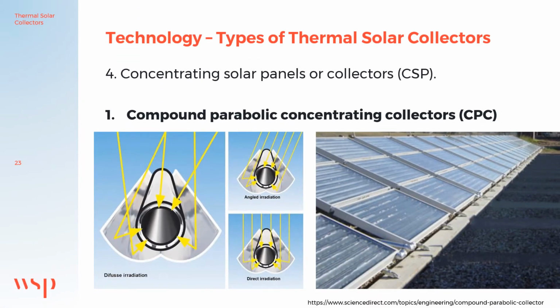The compound parabolic concentrating collector uses an evacuated tube like we've seen before, but with an additional parabolic reflector mounted below the evacuated tube. This directs solar radiation onto all the sides, including the underside of the collector. Compared to a standard evacuated tube, the CPC tube has a much higher efficiency and therefore can supply a much higher heat. CPC tubes require more space on the roof due to the reflector space and require high maintenance for cleaning of the reflectors. The picture on the right shows an additional glass cover over the reflectors to avoid dust collection on the reflector itself.